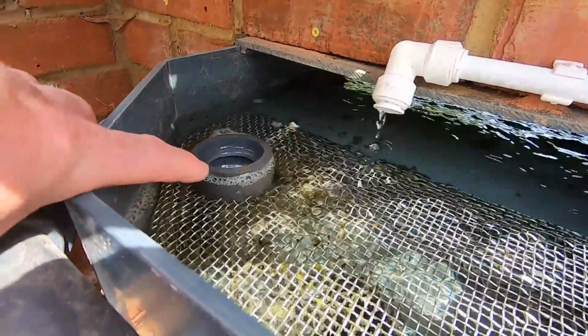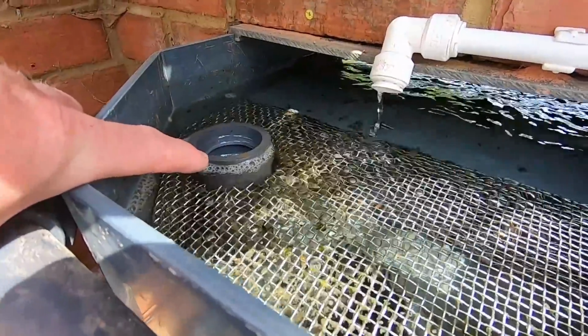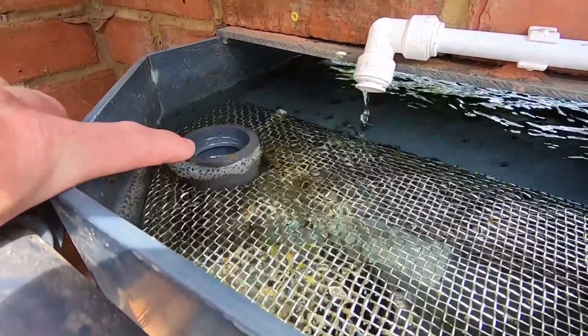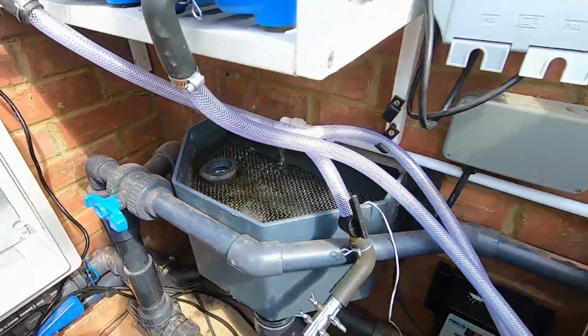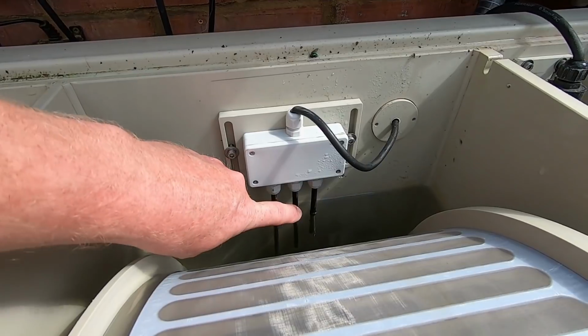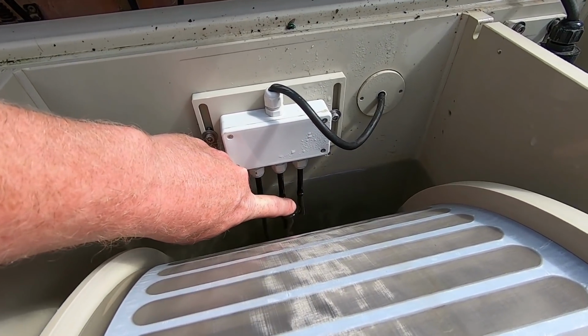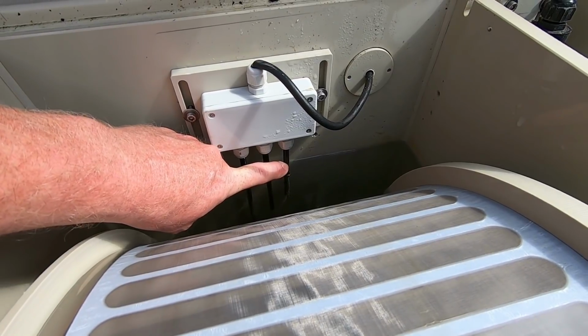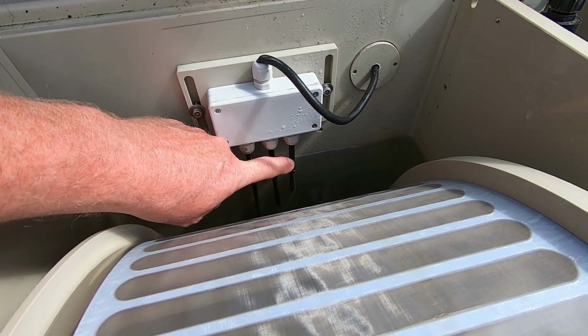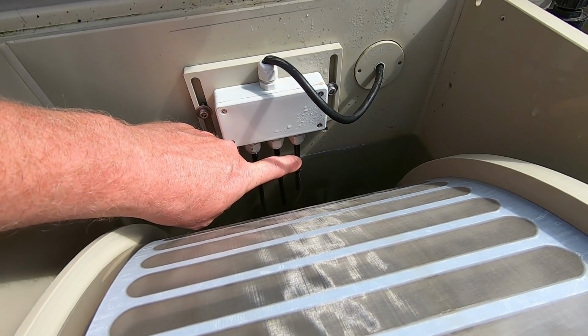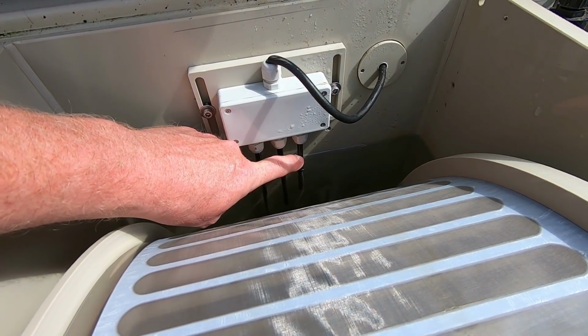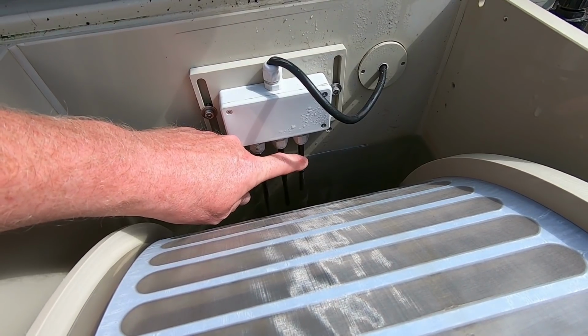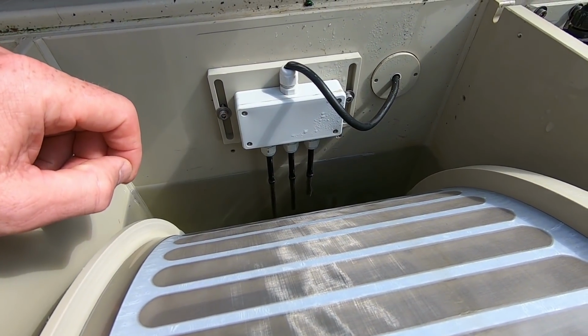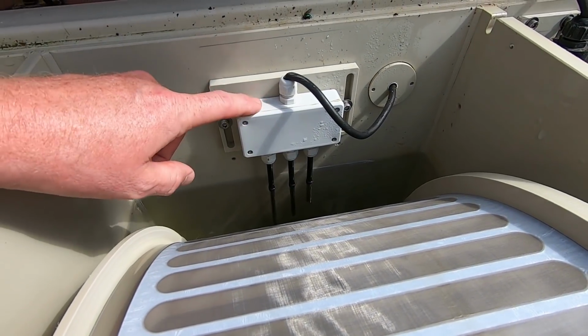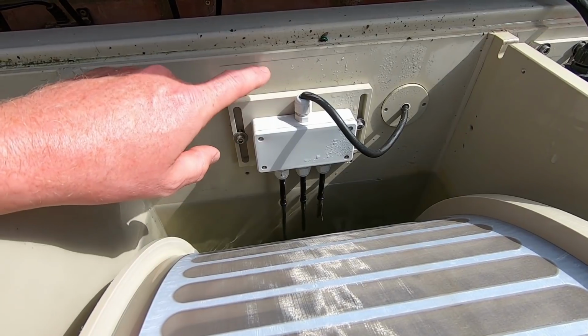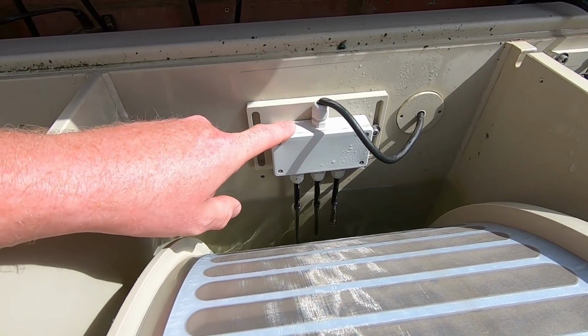So this is about as high as I can get it without the water pouring down the drain, which would clearly be a waste. This is the level probe, and from the tip of the low probe up to, say, this point, the black part of the body, as soon as the drum has had a rinse, that water needs to be 80 mil from there down to the tip, which should give me more dwell time. I have never moved this because it worked, but I've marked it with a pencil line just in case it doesn't work.